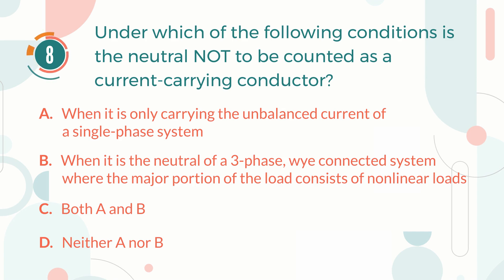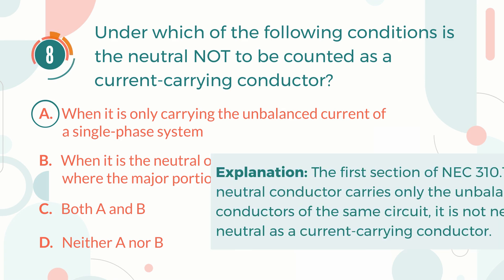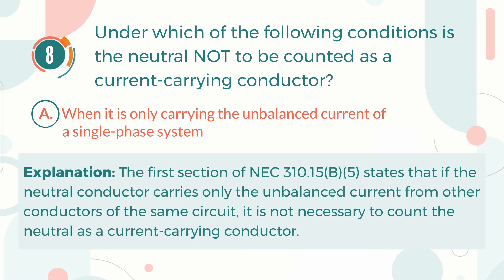The correct answer is A. When it is only carrying the unbalanced current of a single-phase system. Explanation: The first section of NEC 310.15(B)(5) states that if the neutral conductor carries only the unbalanced current from other conductors of the same circuit, it is not necessary to count the neutral as a current-carrying conductor.